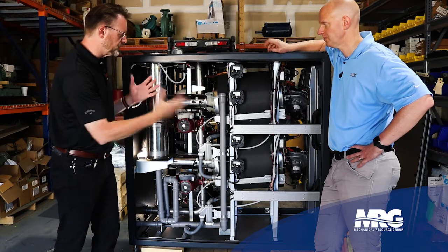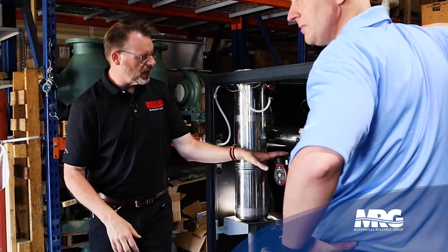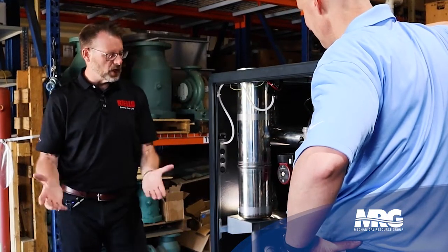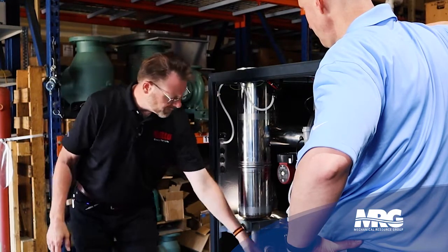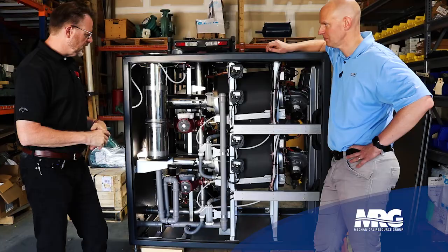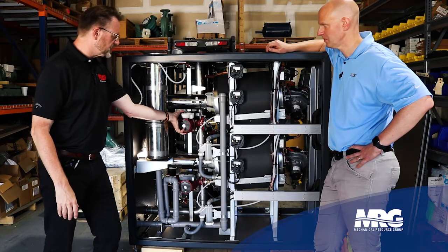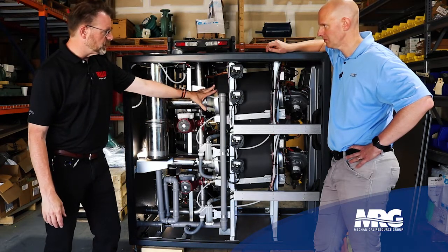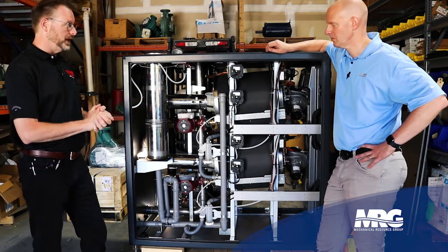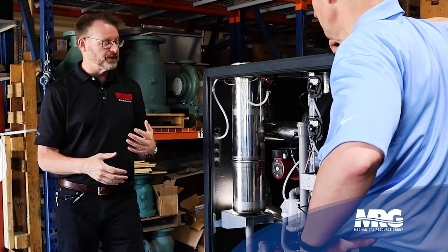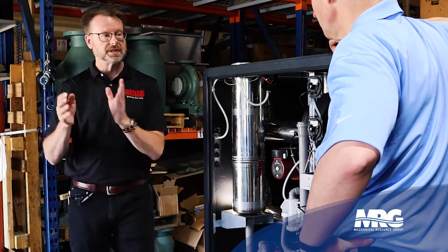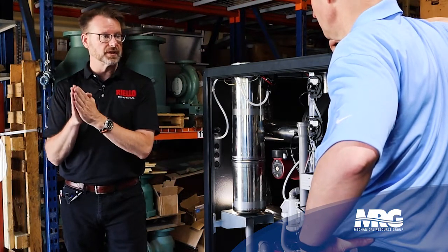We circulate water as well. The heat engine concept, we do that from the factory. We're going to flow the fired heat exchanger with a circulator. Each of the heat engines has its own circulator, and everybody's familiar with the Grundfos circulator. They're very common, they're very prevalent. In that situation, the failure of a circulator would have taken down a single heat engine, and the other heat engines would have continued to operate, which in that case would have left Array at partial capacity, whereas it left that specific boiler down completely.